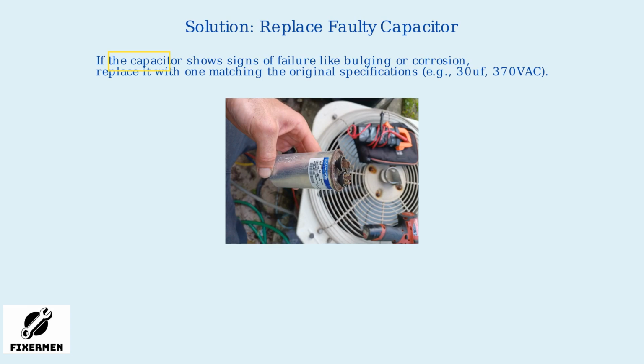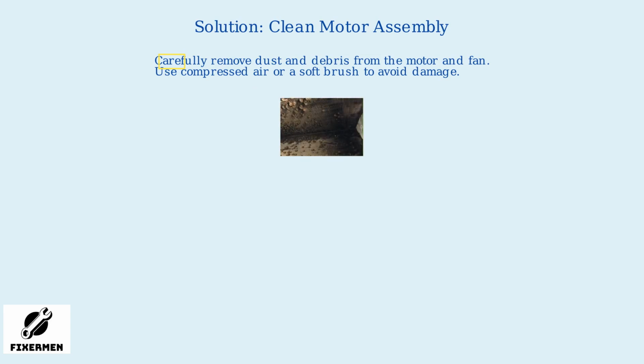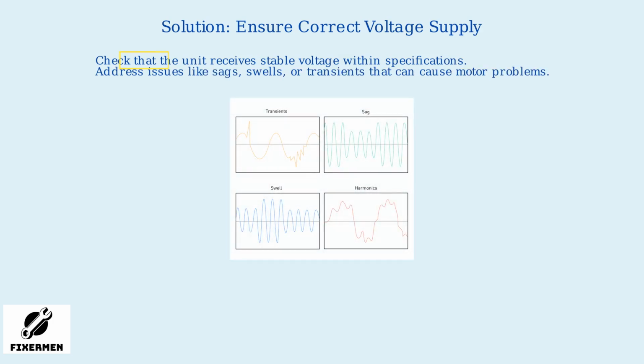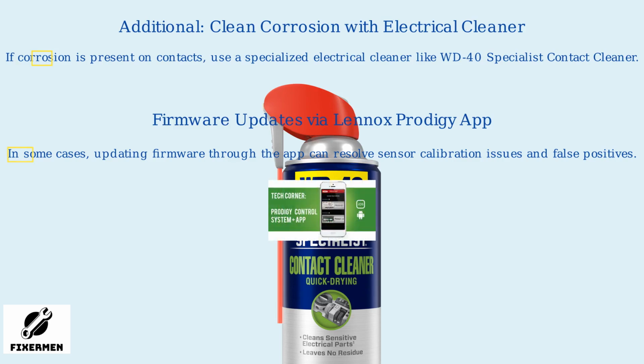For capacitor failure, look for bulging, leakage, or corrosion. Replace the faulty capacitor with an identical one to restore proper motor function. Motor degradation from dust buildup can be addressed by carefully cleaning the motor assembly. Use compressed air or a soft brush to remove accumulated dust without damaging components. For voltage fluctuations, verify the unit is receiving correct and stable power. Problems like voltage sags, swells, or transients can disrupt motor feedback and trigger the H6 error. For corrosion, clean contacts with a specialized electrical cleaner. Additionally, firmware updates available through the Lennox Prodigy app can fix sensor calibration problems and prevent false H6 triggers.